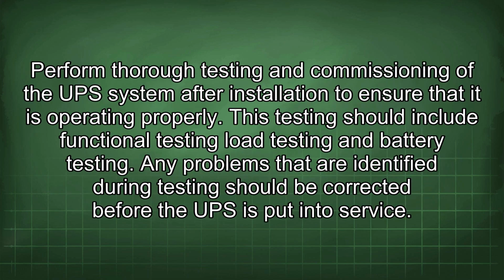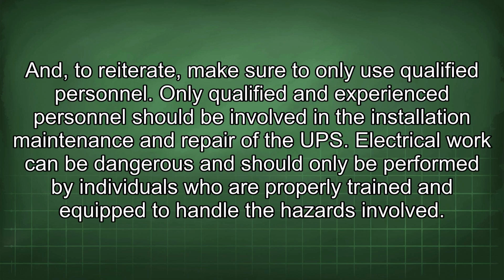Perform thorough testing and commissioning of the UPS system after installation to ensure that it is operating properly. This testing should include functional testing, load testing, and battery testing. Any problems that are identified during testing should be corrected before the UPS is put into service. And, to reiterate, make sure to only use qualified personnel.